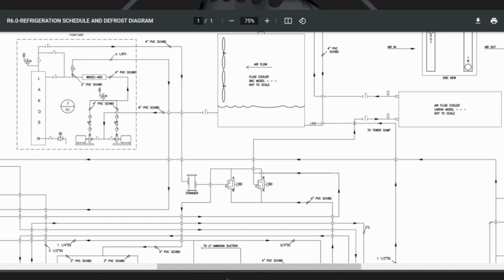Gotcha. So you're positively charging the particles so they stick together, and that in turn makes the particles bigger because now they're collecting to each other, and then the Lakos basically catches all that debris and gets blown out through the 1.25 inch line at the bottom, correct? Well, that's not quite correct. The particles don't get together. The particles stay separated, but they attract the calcium carbonate out of the water. Okay. And rather than settling on the pipe, it settles on this particle. And then when that particle gets enough calcium carbonate in it to be 45 to 65 microns, then it gets separated out by the Lakos.